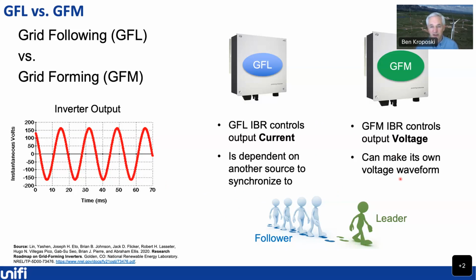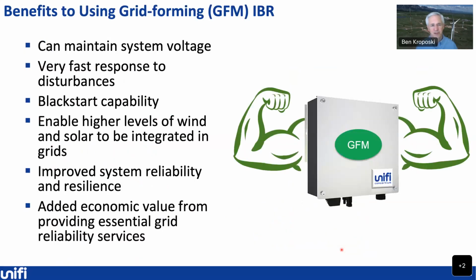It can make its own waveform without another synchronous device, but it can also synchronize to existing devices that are providing the AC waveform for the grid. But again, depending on the conditions it has, it can be a leader for the system and operate the grid from there. There's a variety of benefits for using these grid forming inverter technologies, including maintaining the system voltage, having extremely fast responses to disturbances, the black start capability.